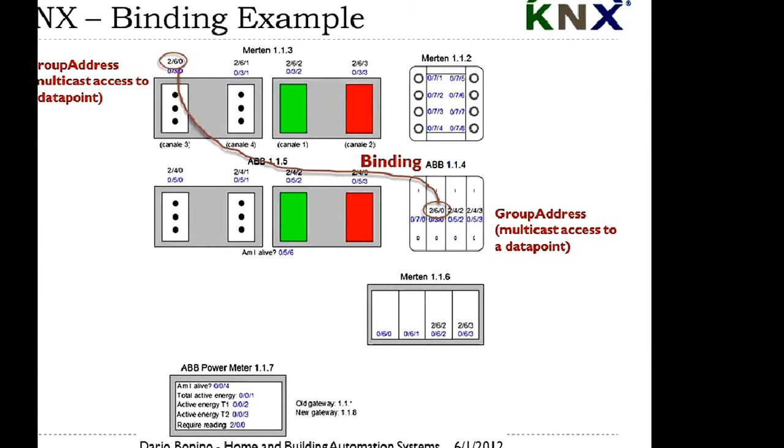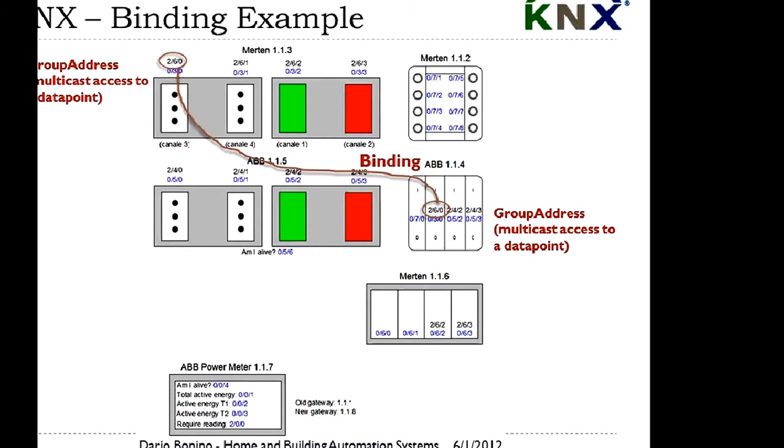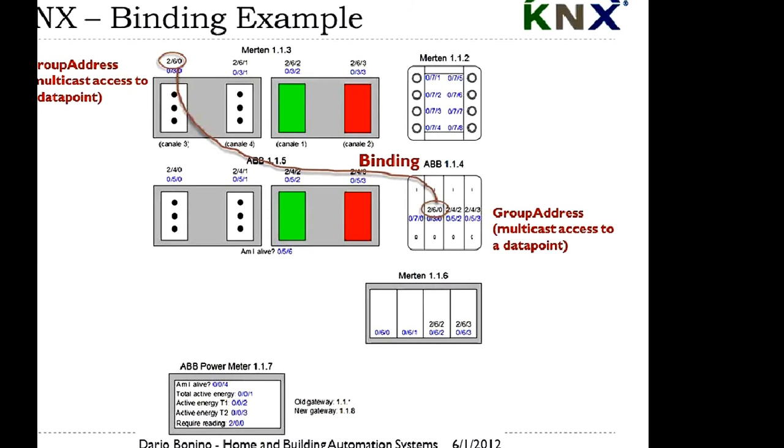And that's why you see here those addresses written in blue. All of them are open bindings, some bindings without the corresponding data point on the other side, that we use for listening information on the devices. In this case, for example, we can deduce that we can listen for button pressure. But this can only be done if we configure a proper binding on the device. Okay.